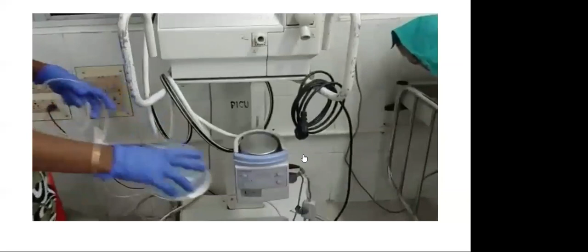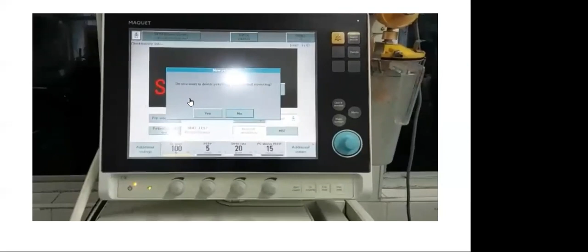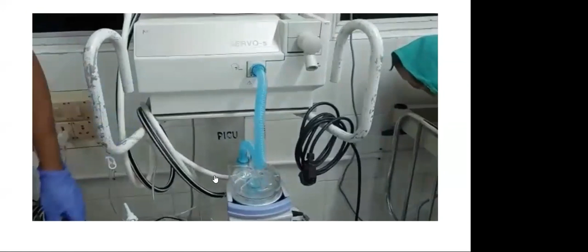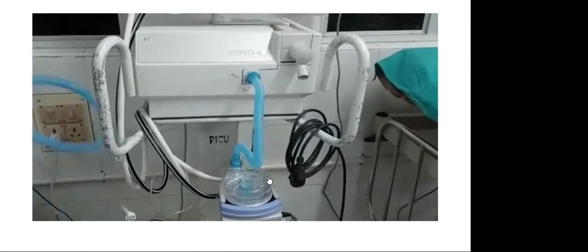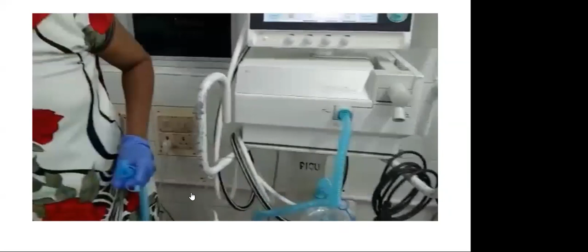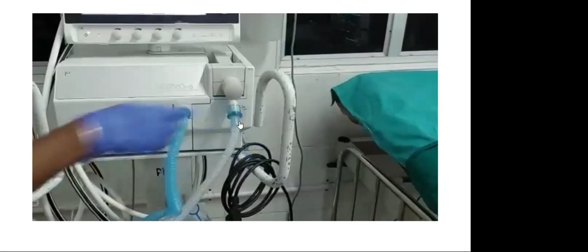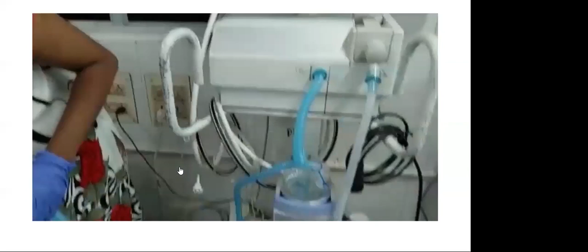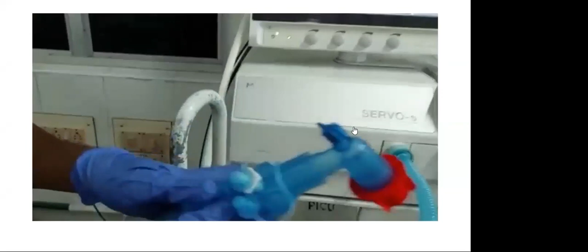So she's connecting the humidifier and the other parts. If you want to keep any previous patient data, you can keep it, otherwise not. So the humidifier is connected to the ventilator, you can see here. And from the humidifier, the inspiratory limb is coming. This is the expiratory valve port where the expiratory limb is connected, and both are connected through the Y piece, the Y connector. And this will go to the patient.